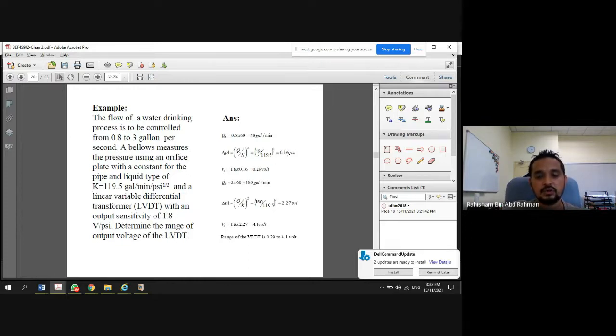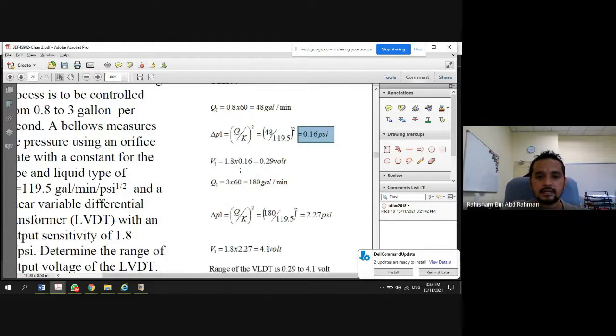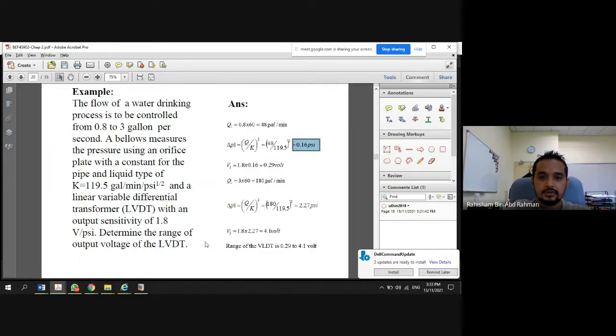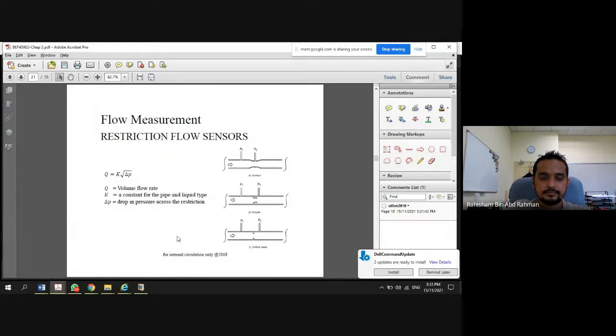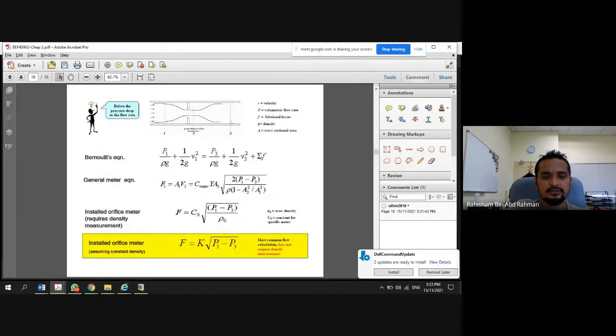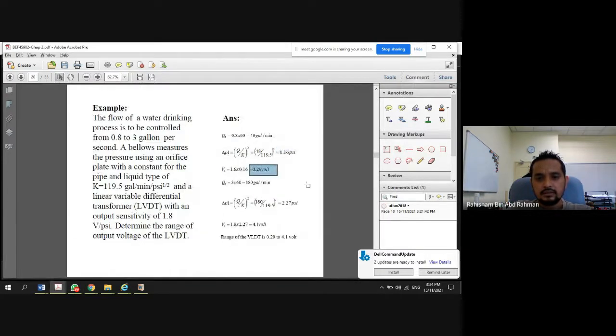So we know this one is 0.16 PSI. So what we have to do is we can actually multiply the sensitivity times the pressure difference. Okay, so that gives you 1.8 times 0.16, and that will give you 0.29 volt. Okay, so what happened in this case within the pipeline? The one that you see in this device will actually show you, with the pressure difference, the voltage will be 0.29 volt. This is the one that you see.